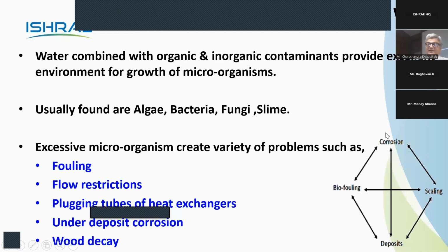This diagram is connected with cooling water, and cooling water is more connected with these bacteria: corrosion, biofouling, deposit, and scaling. These are the 4 issues cooling water faces. If I solve only the problem of corrosion, the problem doesn't get solved because they are interconnected in nature - corrosion will reappear even if you have solved it. So in case of cooling water, you have to take a holistic view of solving all 4 issues together; you cannot just solve one. Similarly, for microorganisms, you have to take care of algae, bacteria, fungi, and slime all together.